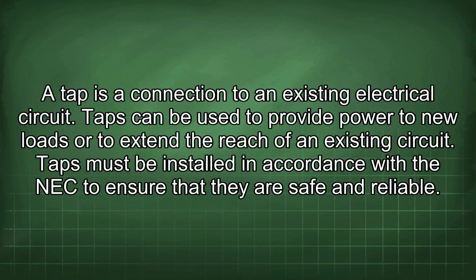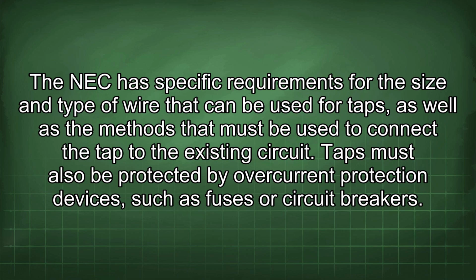A tap is a connection to an existing electrical circuit. Taps can be used to provide power to new loads or to extend the reach of an existing circuit. Taps must be installed in accordance with the NEC to ensure that they are safe and reliable. The NEC has specific requirements for the size and type of wire that can be used for taps, as well as the methods that must be used to connect the tap to the existing circuit. Taps must also be protected by overcurrent protection devices, such as fuses or circuit breakers.